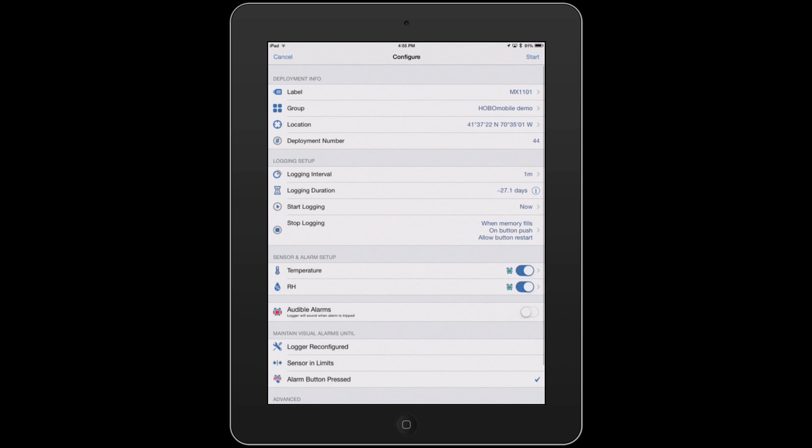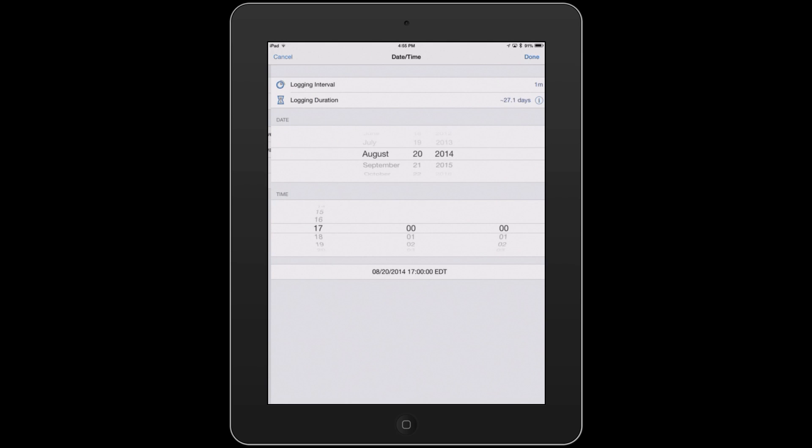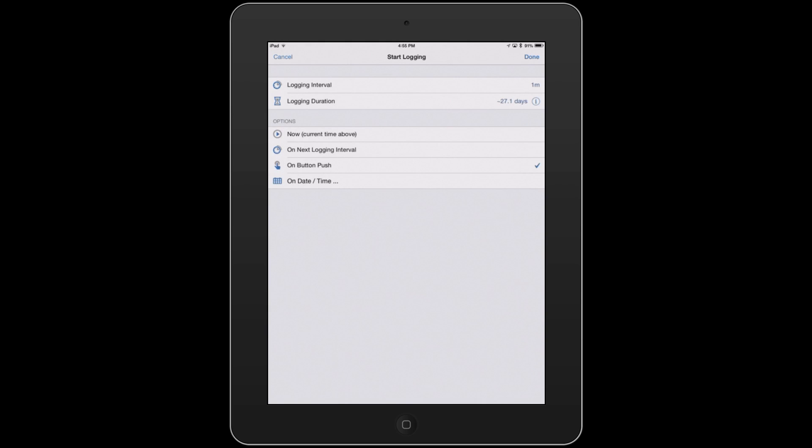You can set how you want the logger to start. So there's a couple different start logging options, whether you have it start now at the next one minute interval, you can have it start with a push button, or you can have it start on a particular date and time. We'll go back and just have this start recording now, and we hit Done.